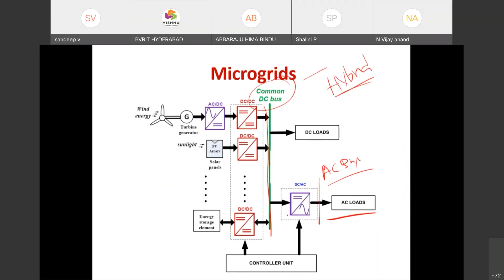And what are the main goals particularly in grid connected renewable energy sources? When you connect to the grid, one is to coordinate active power and reactive power dispatch, current unbalance and balancing, and current harmonic compensation. And when you try to go into disconnected mode, then what will happen is a sudden change. The phases of these voltages cannot be controlled, so obviously we will find some kind of voltage rise or dips. Mostly voltage rise will be there.